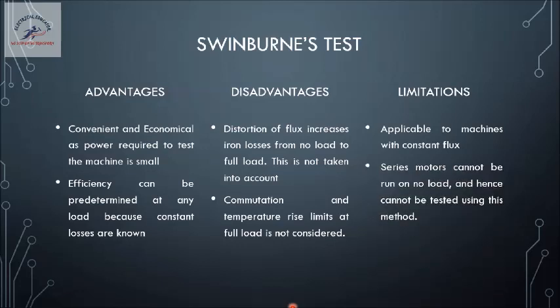Series motors cannot be run on no load, and hence cannot be tested using this method. While discussing the characteristic of series motor, we have seen a hyperbolic curve, speed versus torque. There we had a small discussion that if a DC series motor is run on no load, it will attain a dangerously high speed, thus damaging the armature. And Swinburne test is specifically performed at no load. So it is not possible to test a series machine using this technique.